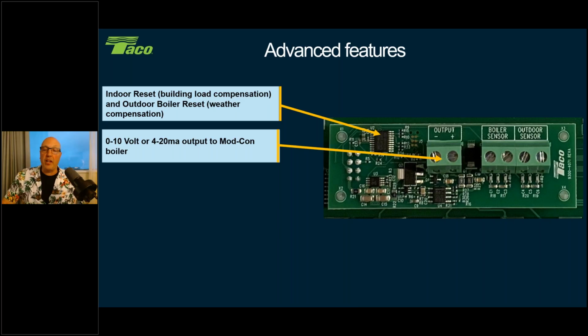Now we have this terminal on here that says 0 to 10, plus and minus, and this is an output, all right, where we can go and talk to something else and give it a 0 to 10 volt signal or a 4 to 20 milliamp signal output. And if you're not sure what 0 to 10 volt signal means, it's a calculation that's done by the board itself. If it were to send a 10 volt signal across those two wires, that means whatever it's talking to should run at 100%. If it sends 5 volts out to it, it should run at 50%. So it's just that relationship out there.